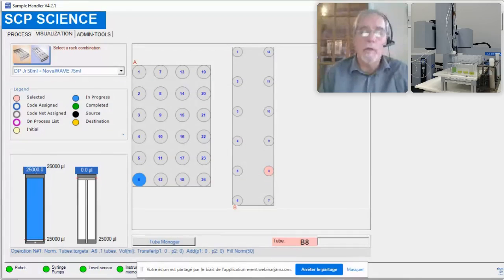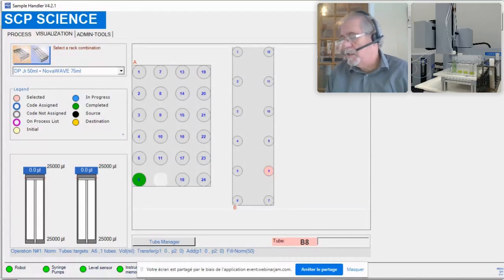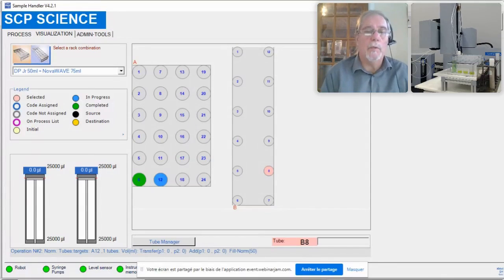Some of the assumptions are that all of the tubes are identical. So digitubes are made by injection molding. So we're looking at tubes that are made similarly with a graduation. So you can see that AccuNorm has added the volume to the system, to the tubes. The way that AccuNorm works is that it takes a measurement, does the mathematical calculations, adds 80% of the diluent on the first pass, then remeasures in the center of the tube in the meniscus to do another determination of the amount of liquid required to finish off to the 50 mil mark. That's how AccuNorm works.